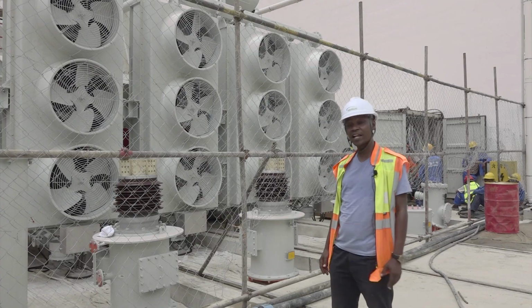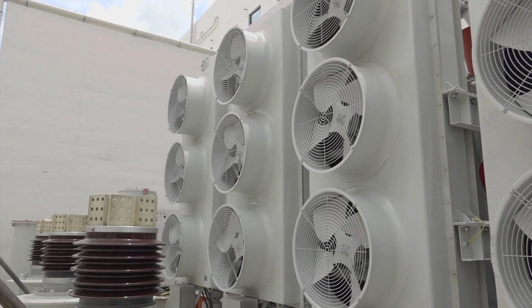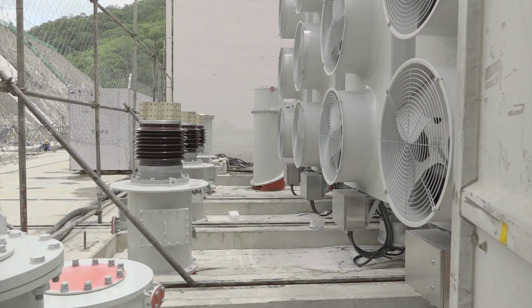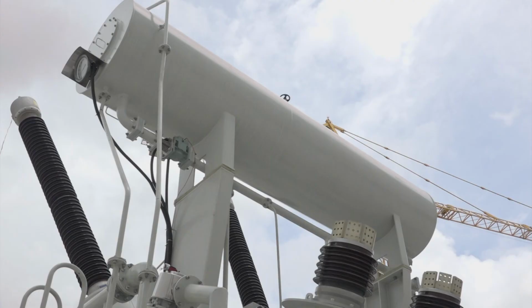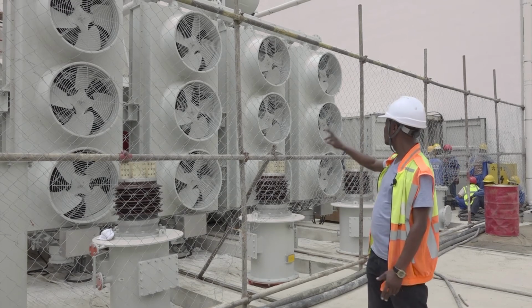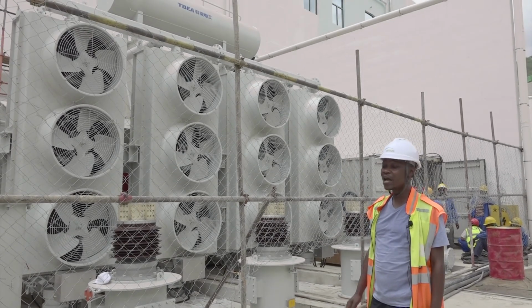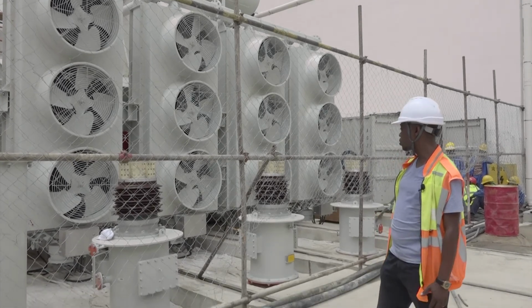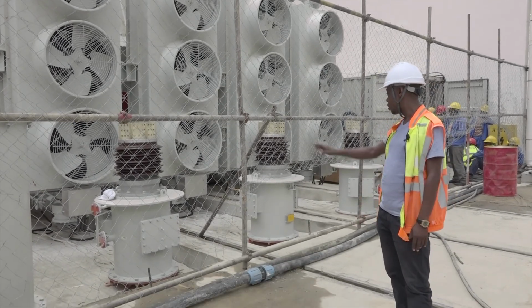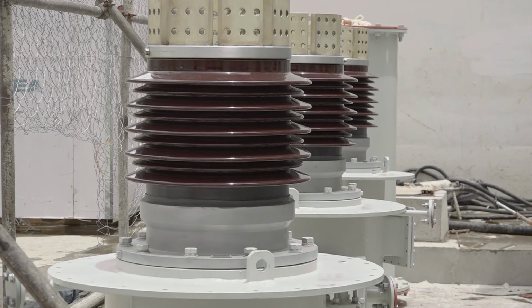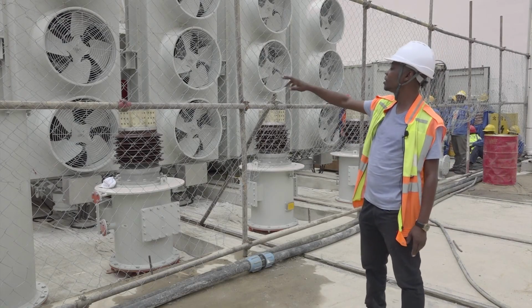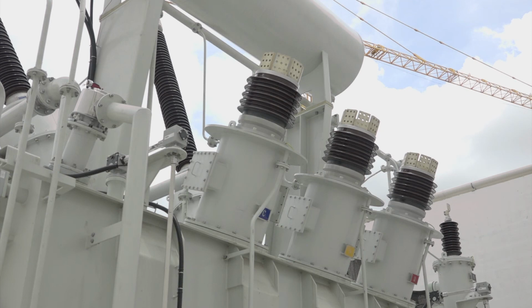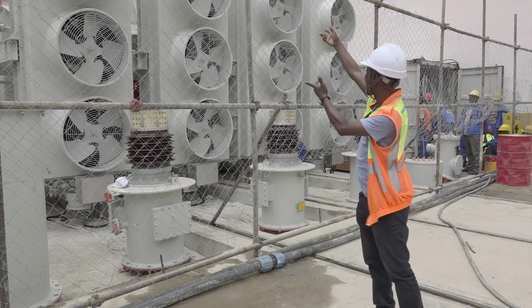Our generator units will be generating 13.8 kilovolts. This is the cell for transformer number 2. As you can see, the air coolers have already been assembled, the conservator tank has already been assembled, and most of the pipe work has already been done. Now we are waiting to assemble the low voltage bushings, which are these we are seeing, and also the high voltage bushing assembly, which will be in front, behind these.